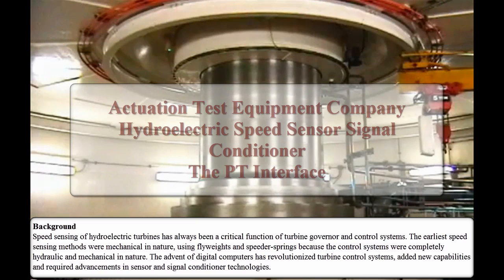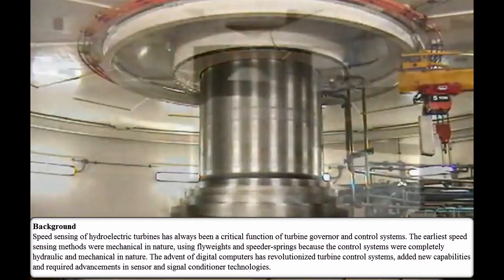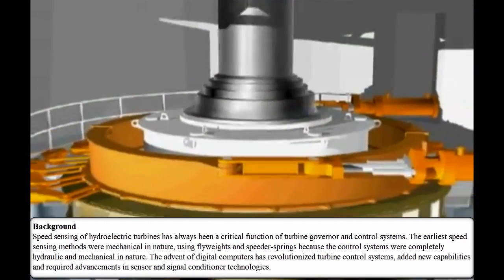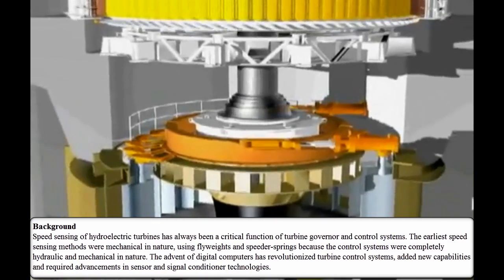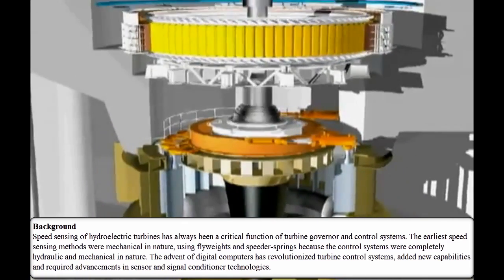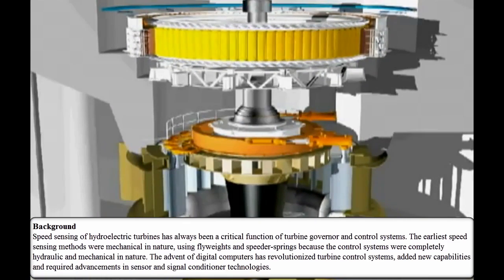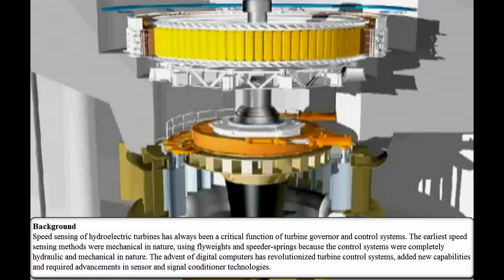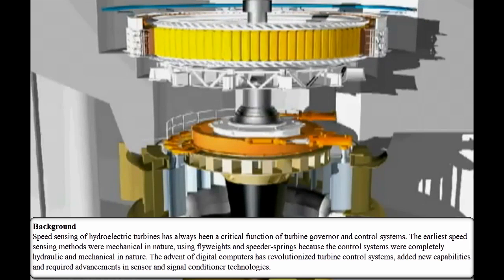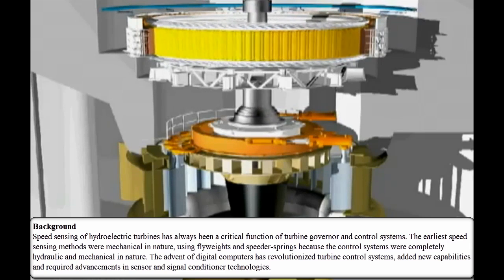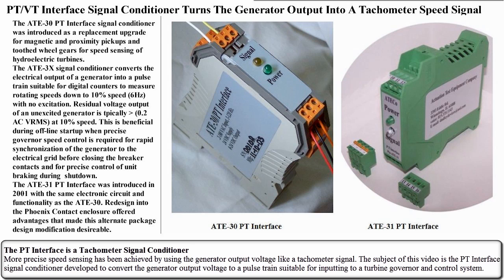Speed sensing of hydroelectric turbines has always been a critical function of turbine governor and control systems. The earliest speed sensing methods were mechanical in nature, using flyweights and speeder springs because the control systems were completely hydraulic and mechanical in nature. The advent of digital computers has revolutionized turbine control systems, added new capabilities, and required advancements in sensor and signal conditioner technologies. More precise speed sensing has been achieved by using the generator's output voltage like a tachometer signal.